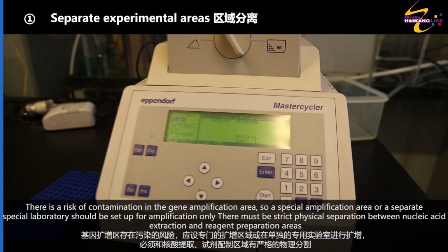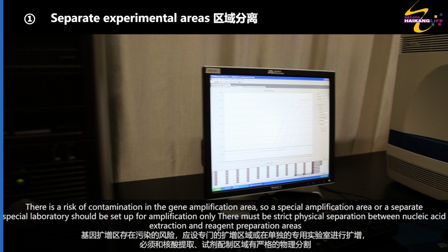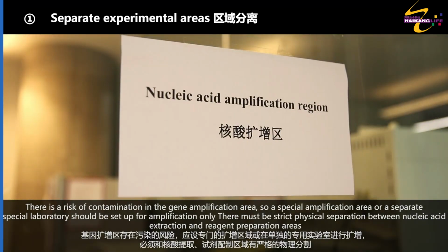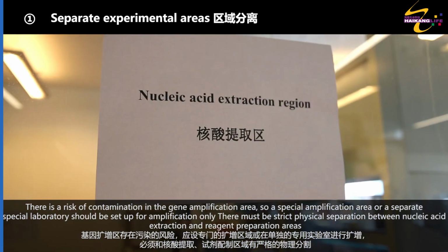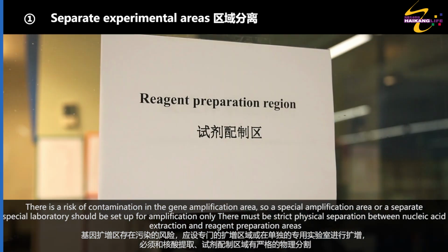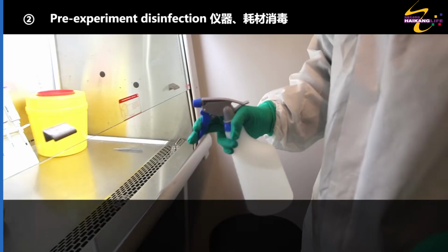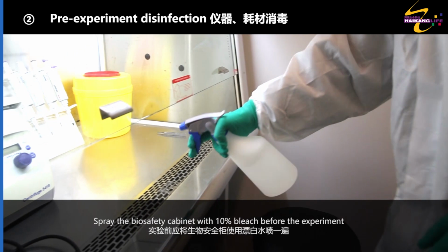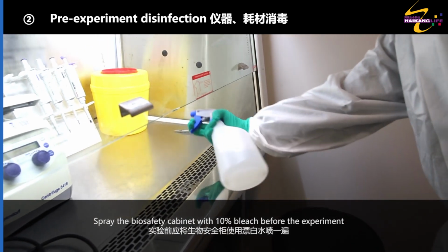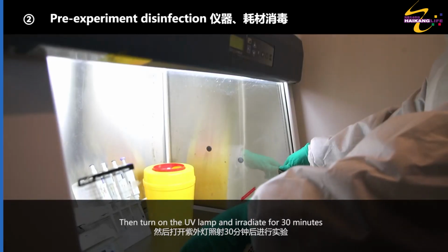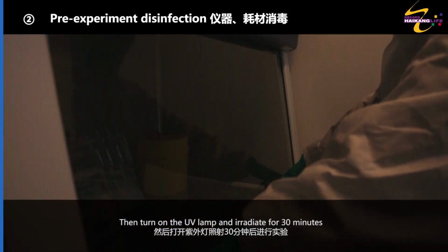There is a risk of contamination in the gene amplification area, so a special amplification area or a separate special laboratory should be set up for amplification only. There must be a strict physical separation between nucleic acid extraction and reagent preparation areas. Spray the biosafety cabinet with 10% bleach before the experiment. Then turn on the UV lamp and irradiate for 30 minutes.